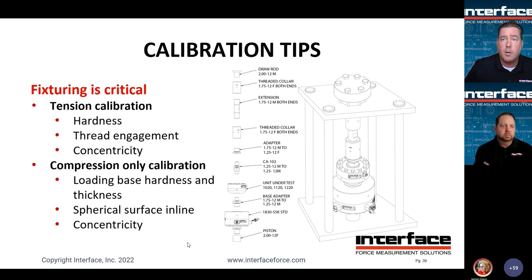Calibration fixturing. This is a critical step. And a lot of times you can see errors pop up in calibration that may not be readily explainable, that can be traced back to different issues with fixturing. This can be anything from pre-tensioning a jam nut to something that's bent to something that's starting to fatigue. So what you see here on the right is an example of a load string. This is typical for one of our load frames, and we have a series of adapters, threaded adapters, I should add, to adapt to the myriad, I should say, of different thread options that exist out there.